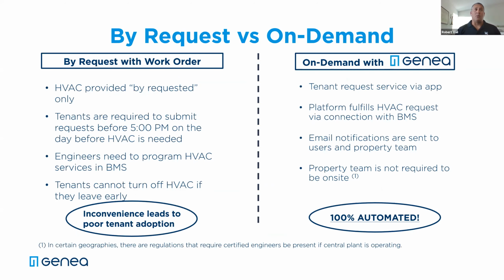There's a significant difference between by request and on demand. Most buildings without a system like ours require tenants to submit a request to turn on air by 5 o'clock the night before, and the engineer has to program the building automation system—but tenants can't turn anything off if they leave early. We're in a different world now where people's plans change, with kids or a spouse at home, so you may end up running the building unnecessarily.